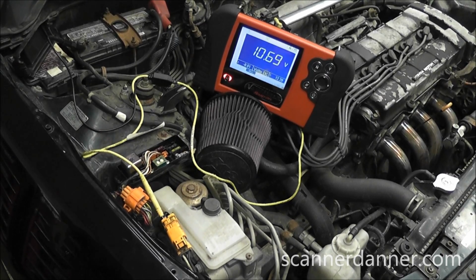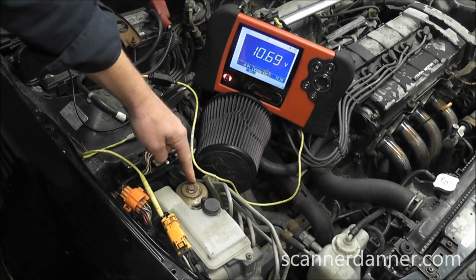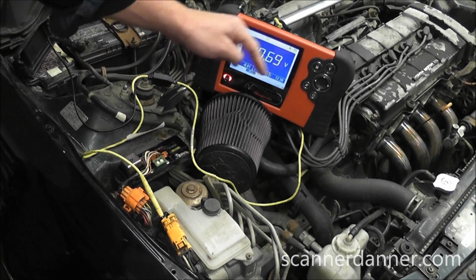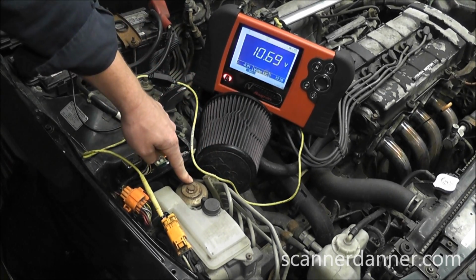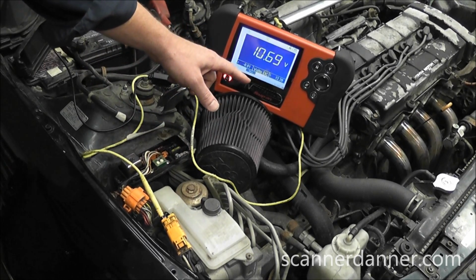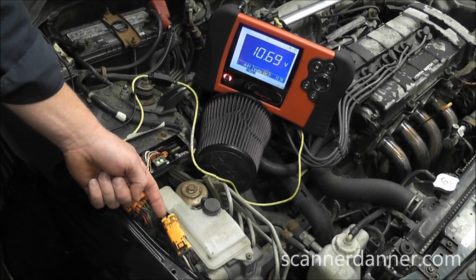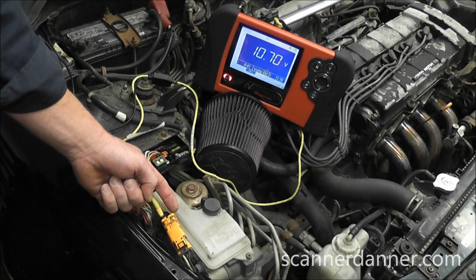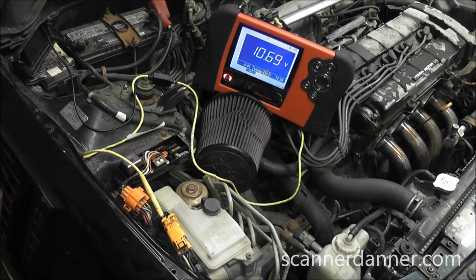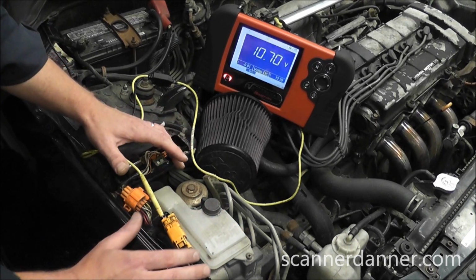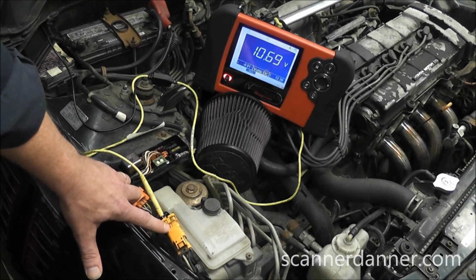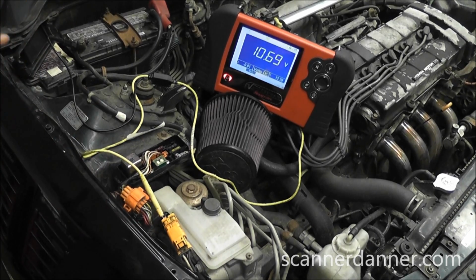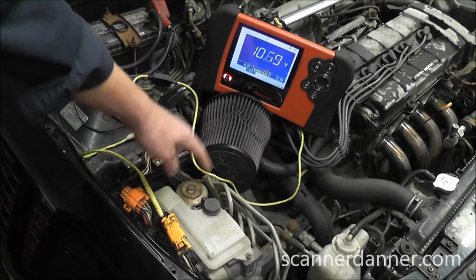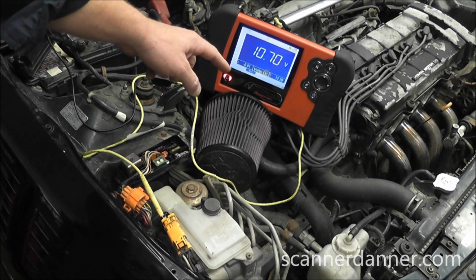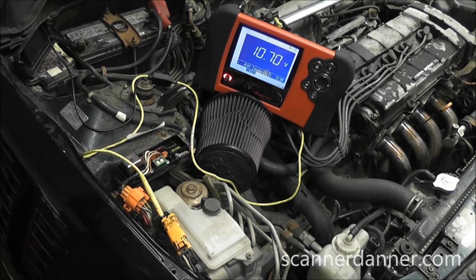We're pretty confident what we're looking at here is a bias. At this point I actually smacked on the motor. The thought process is that this bias line gets pulled to ground through the brush motor contacts, so either our brush motor contacts are faulty or we have a bad ground. The ground test would have been to back probe the ground and look at voltage with the circuit energized - it was low, so that wasn't our problem. Unfortunately I can't simulate that directly. What I have right now, and didn't tell you before, is this connector unplugged a little to simulate what we saw. At this point, again, we smacked on the motor and it dropped to 0 volts - we were correct in our assumption. It was a bias voltage, and our motor circuit is internally faulty.